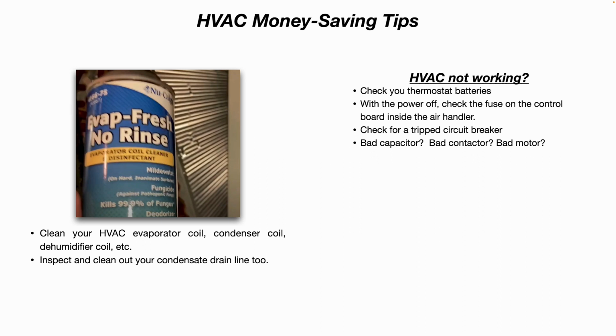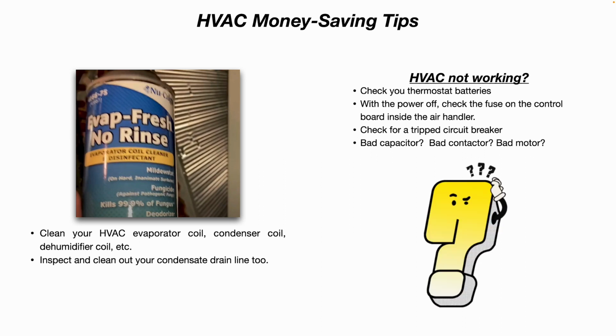Is your HVAC system not working? Well, check your thermostat batteries. Are they dead? With the power off, check the fuse on the control board inside the air handler. There's usually a 3 or 5 amp blade fuse. Check for a tripped circuit breaker at your panel. Do you have a bad capacitor, a bad contactor, a bad motor?